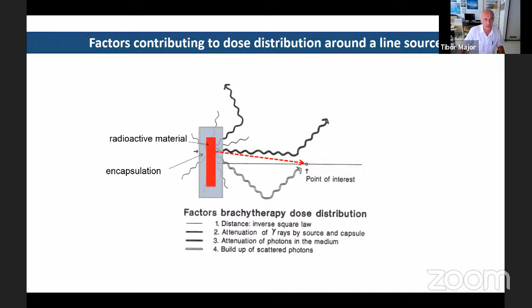But in clinical practice, we don't use point sources, we use very small line sources. Here you can see the factors contributing to a dose distribution around the line source. This is the radioactive material, and this is encapsulated, a small capsule. And this is the point of interest, and these four factors determine the dose at the reference point: the distance, which follows the inverse square law for a very small point source; the attenuation of the gamma rays by the source and the capsule itself; the attenuation of the photons in the medium; and the buildup of the scattered photons. These factors have to be taken into account during the dose calculation.